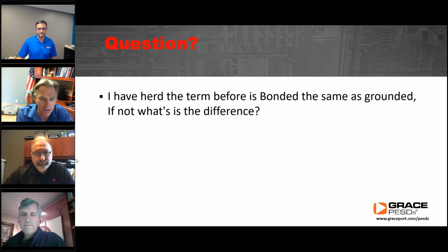Where this information comes from, they are not the same terms. Bonded or bonding is defined in Article 100 of NFPA 70. Now, NFPA 70 is what we know as the National Electrical Code. Bonded is defined as connected to establish electrical continuity and conductivity—that's what bonded is. It's to establish electrical continuity and conductivity.